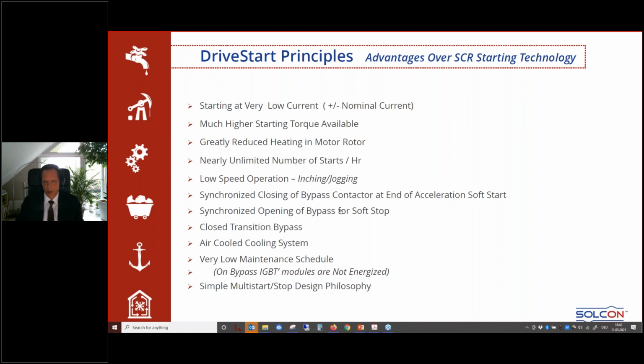We have synchronized opening of the bypass also for soft stop. Sometimes in a pump you need a soft stop. This means you have to extend the braking time in order to eliminate the water hammering effect. Water hammering is when you have a water column on top of the pump and you brake too abruptly, then you can have mechanical resonances in the system which destroy the pump and the piping, and with the soft stop you are eliminating exactly this effect.